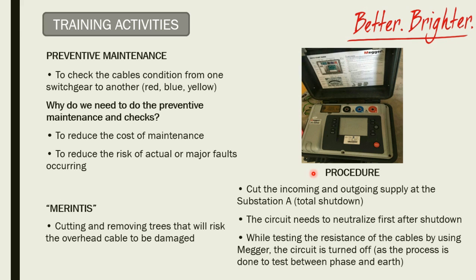Here are the procedures for preventive maintenance. First, we cut the incoming and outgoing supply at the substation, which we call a total shutdown for the switchgear. Then the circuit needs to be neutralized after the shutdown. While testing the resistance of the cables, the circuit needs to be turned off, as this process tests between the phase and earth cable, so the circuit cannot connect to earth.